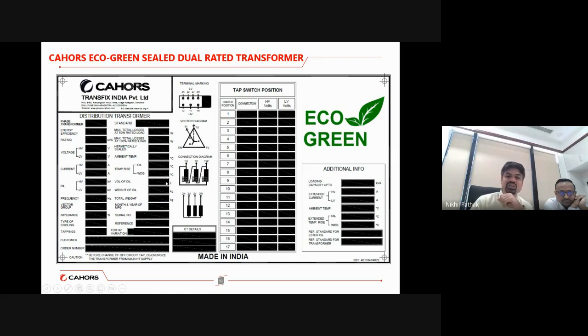that the base rating of the transformer will be operated with the best temperatures. For example, a 2 MVA transformer at 50 degree ambient is operated at 50-55 degree, and the 2.2 MVA transformer, for example, will be operated at 70-75 degree. So the temperatures will be a differentiating factor on the transformer loading. So in this case, your OTI-WTI setting will have to be changed. Otherwise, it will give a tripping command to your breaker if you are overloading the transformer.